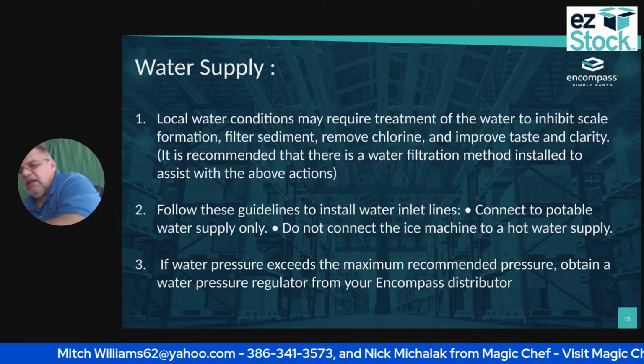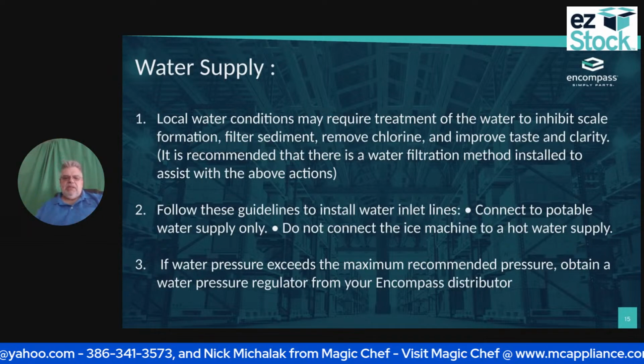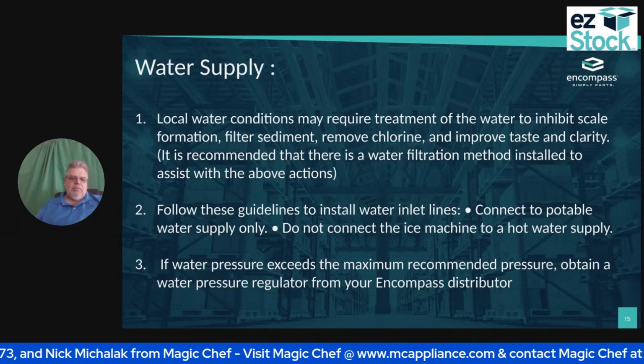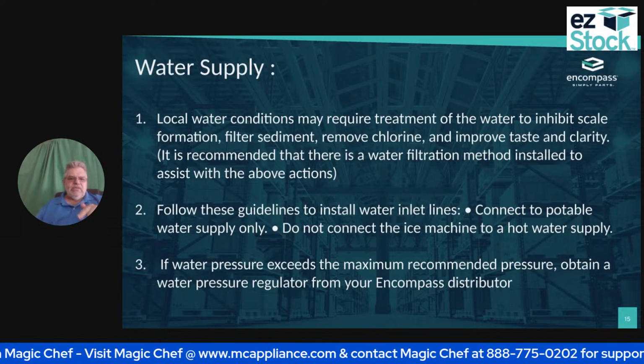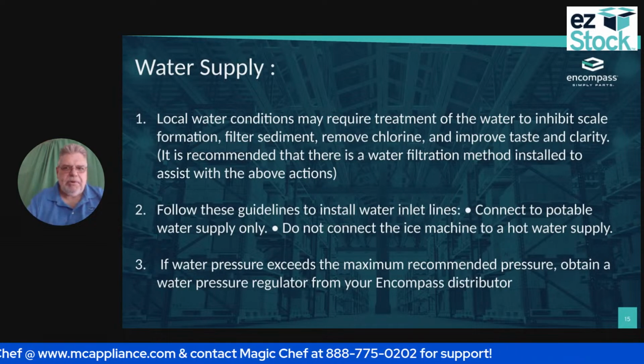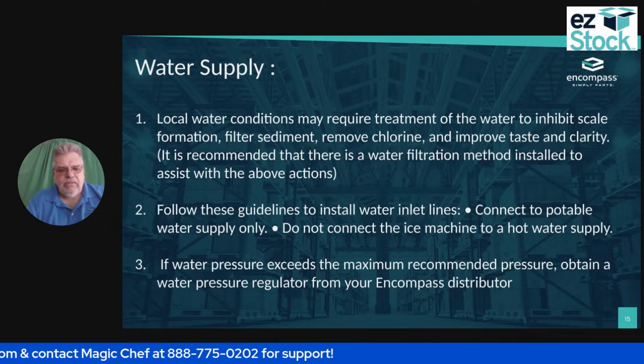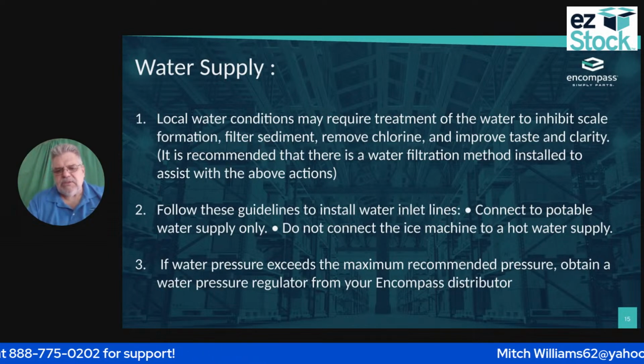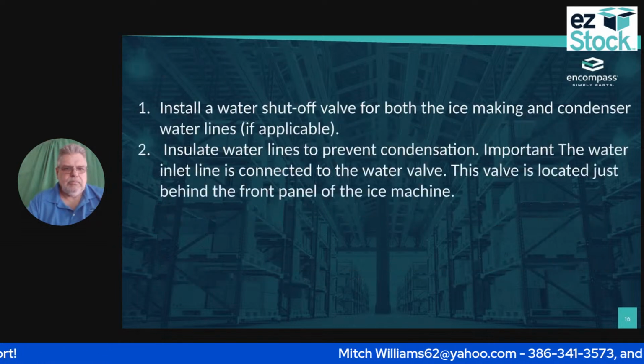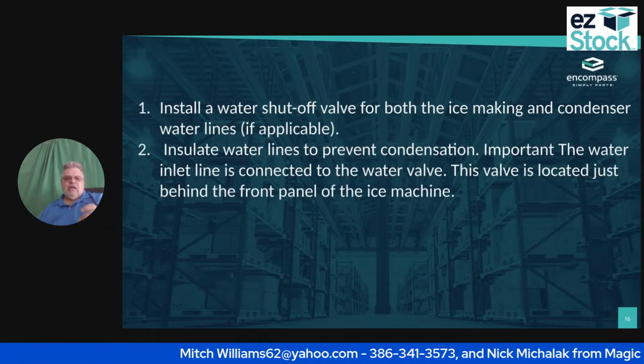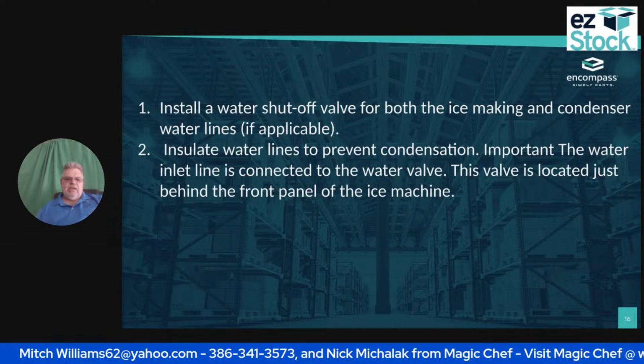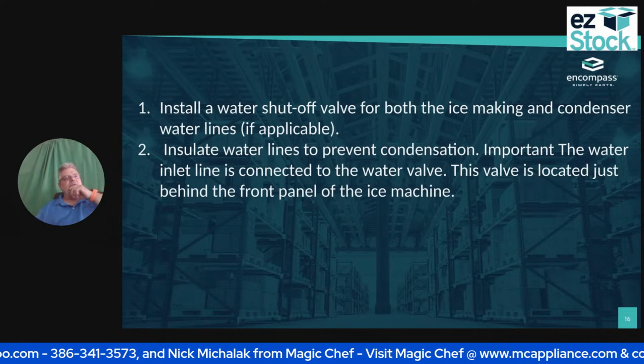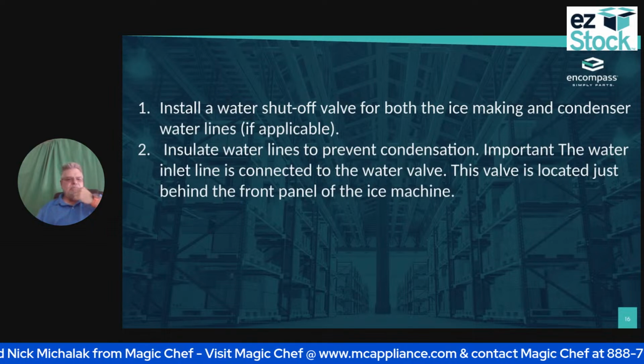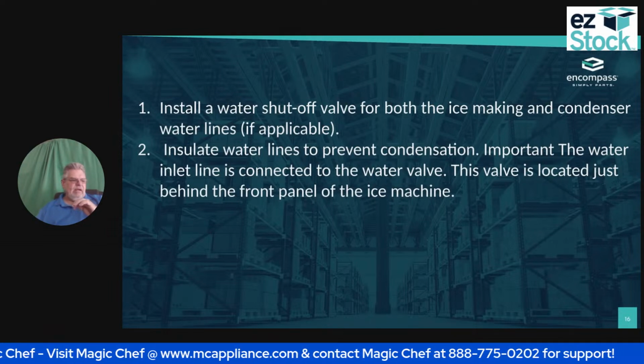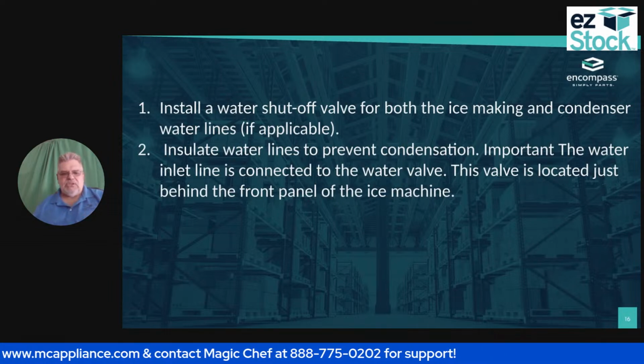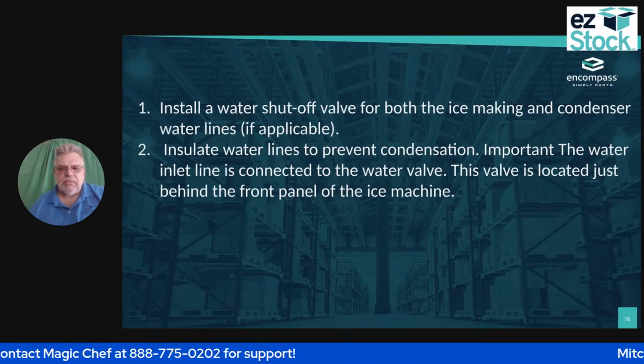Okay, if the water pressure exceeds the recommended pressure, I may have to put in a pressure regulator. You can get that from your Encompass distributor, and they sell that pressure regulator. Okay, I'm going to install a water shut-off valve for both ice making and the condensing water lines if I have a unit that has the water condenser. So I have to have a water shut-off valve for each of those, okay? And then I'm going to insulate the water lines to prevent condensation.